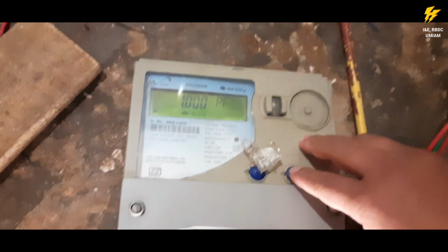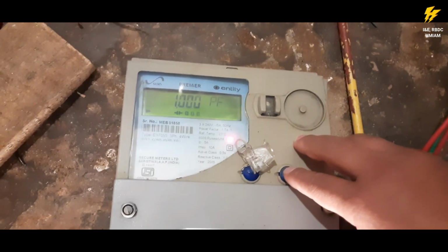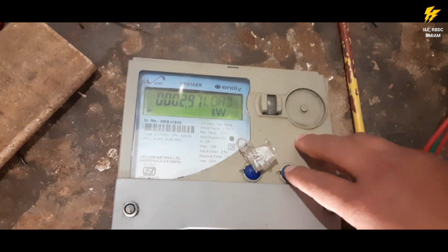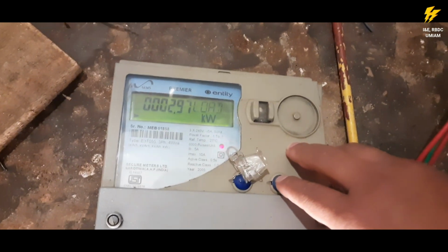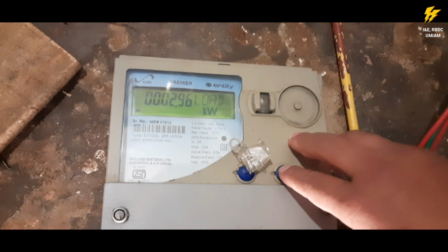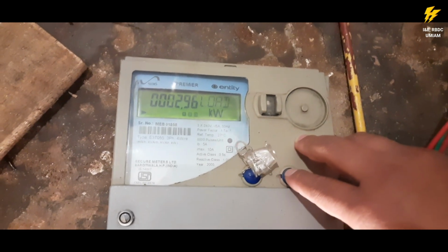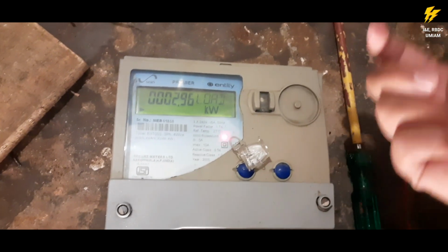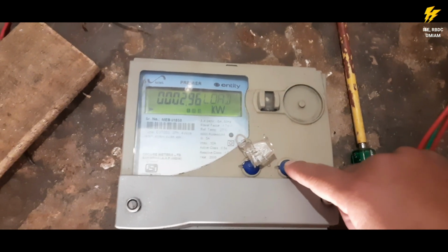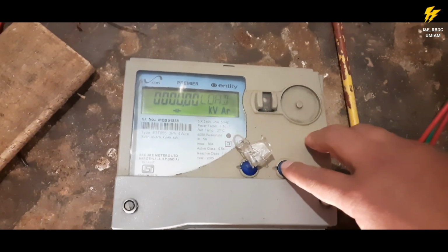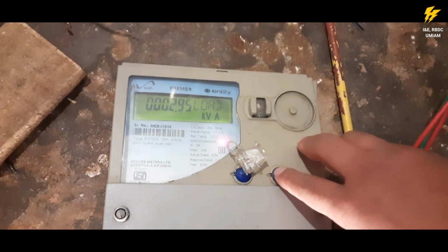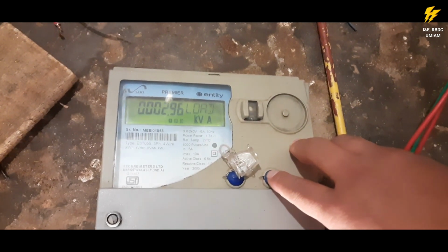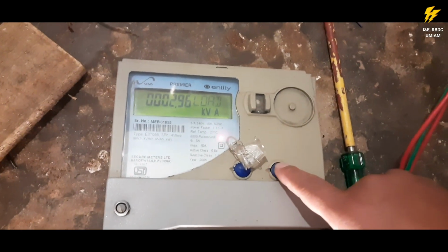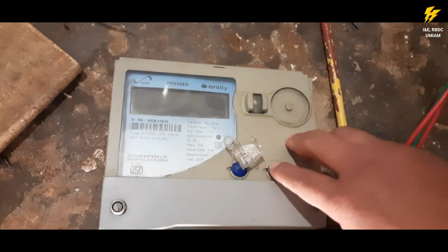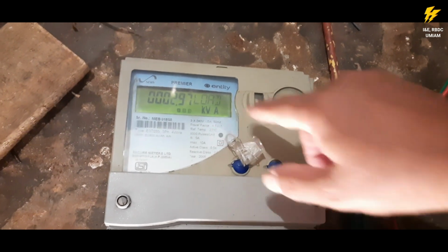And then the power factor, since the load is a heater, which is not a coil, the power factor will be 1. All right, and now the present demand, this is the load. The present demand is 2.96, almost 3 kilowatt, because it's a 1 kilowatt heater for all the 3 phases. You add it, you get almost 3 kilowatt, which is true. Okay, and then in terms of kVA it is 2.95. I thought it wasn't giving kVA, but it actually gives it, which is fine. It can be used for consumers of connected load 50 kilowatt and above also, because you are getting kVA here.